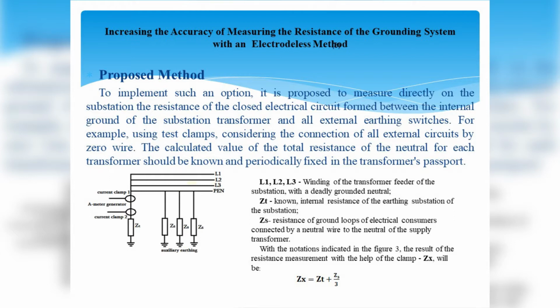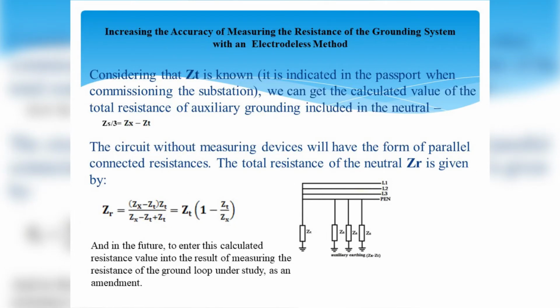This is examined in figure 3, where L1, L2, and L3 indicate the windings of the feeder transformer of the substation with a dead-grounded neutral. ZT is the known internal resistance of the earthing of the substation. ZS is the resistance of the ground loops of electrical consumers connected by a neutral wire to the neutral of the supply transformer. Considering that ZT is known, it is indicated in the passport when commissioning the substation, we can get the calculated value of the total resistance of the auxiliary grounding included in the neutral: ZS / 3 = ZX − ZT. The total resistance of the neutral ZR is given by the formula. And in the future, this calculated resistance value is entered into the result of measuring the resistance of the ground loop under study as an amendment.